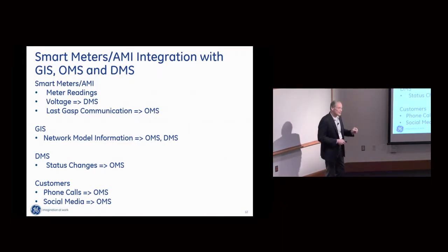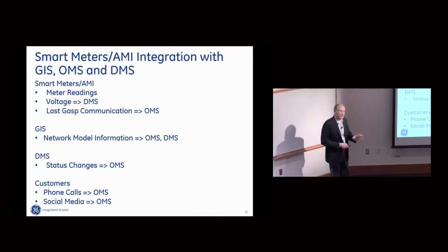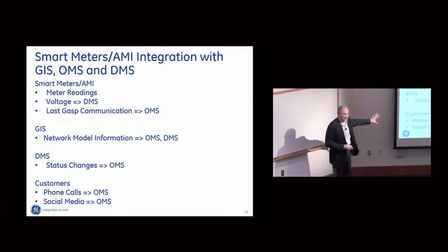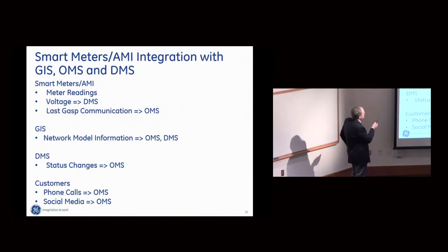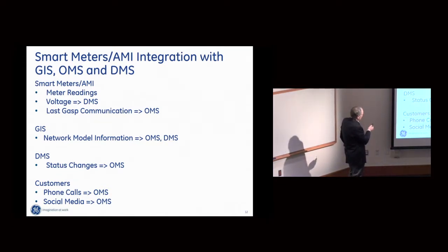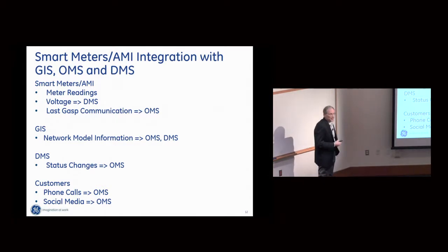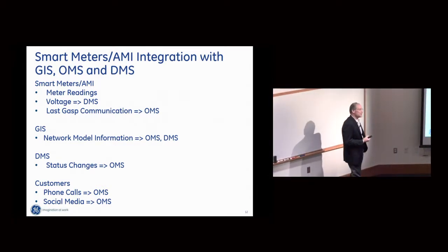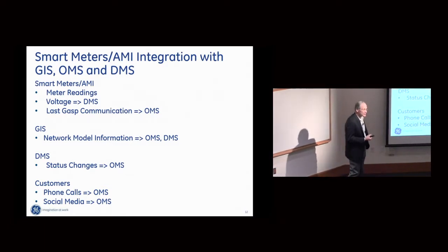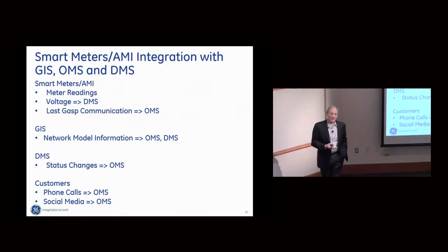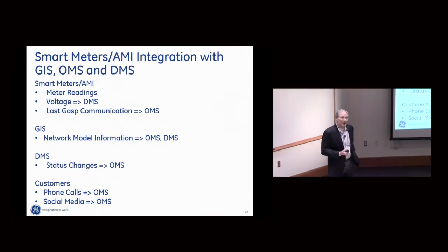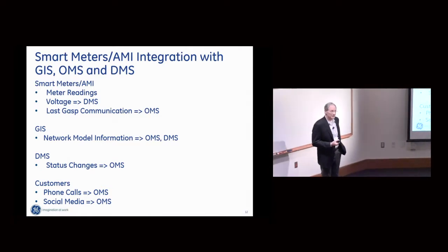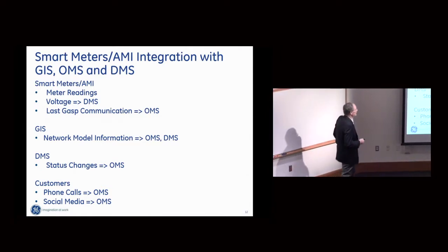A measure of a utility's grid resiliency is directly proportional to how well they've done that integration. For instance, smart meters not only give me meter readings, but I can ping certain meters at the ends of feeders to get voltage readings for the network model in the DMS. If I don't have a smart meter on certain feeders, I need to add end-of-line voltage sensors with two-way communications, because an ANSI standard requires the voltage at the customer's premise to be 120 volts plus or minus 5%. If I'm down near 114 volts on certain feeders, I need to know that margin.